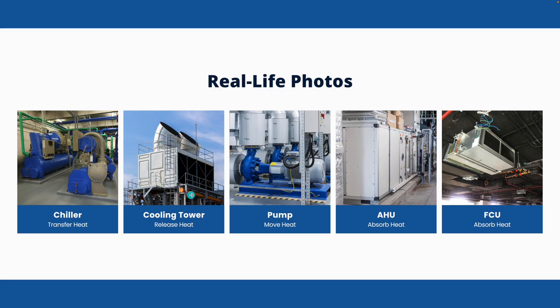Here are some real-life photos to help you understand what each component looks like. This is a water-cooled chiller. Here is a cooling tower — the large unit on the roof. Pumps are quite common. The AHU is the bigger unit, usually sitting on the floor inside a dedicated AHU room because it is large and noisy. The FCU, on the other hand, is hung above the ceiling. Essentially, AHU and FCU absorb heat; the pump moves that heat to the chiller, which transfers it to condenser water; the condenser water goes to the cooling tower to release the heat, cooling the building.